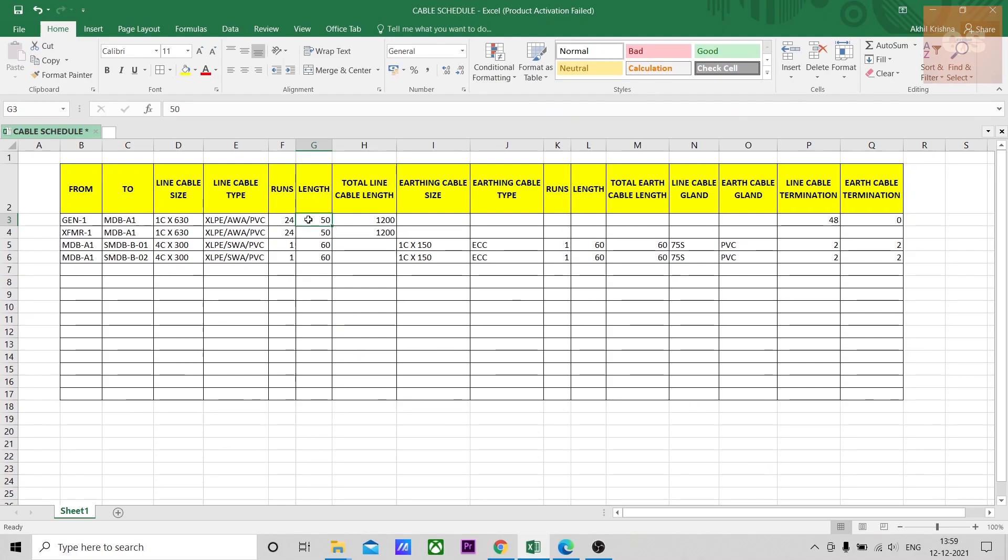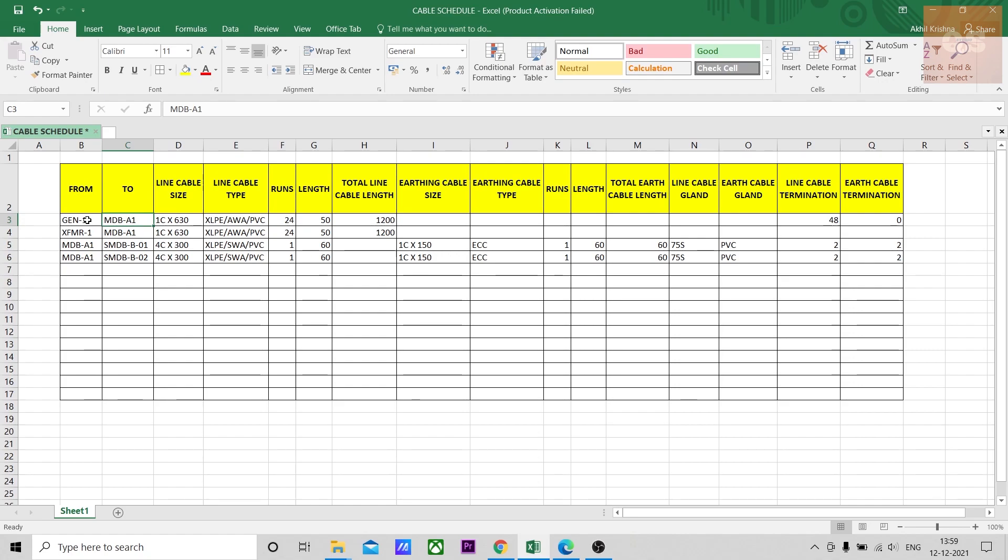For calculating the length, what you need to do is go to the plan and check where generator 1 is and check where MDB-A1 is and measure the shortest distance between these two. That is how you calculate the length. Even if the length is given in the SLD, it is your duty as a QS to make sure that the length given in the SLD is right or not. Sometimes the length given in the single line diagram will not be accurate.